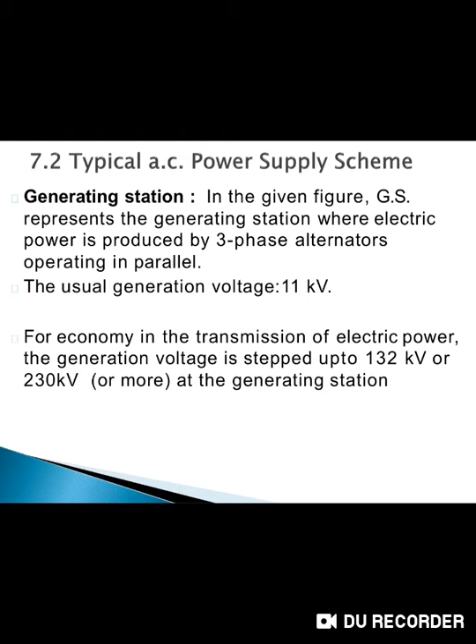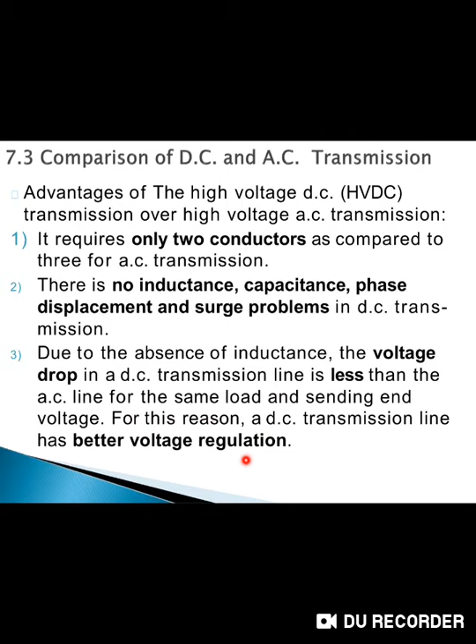We have already known the electrical supply system can be broadly classified into two types, that is AC or DC system, overhead or underground system. Comparison of DC and AC transmission. First, we have to know the advantages of DC transmission when compared to AC transmission. First point, HVDC transmission requires only two conductors as compared to AC transmission. Here, there is no inductance, capacitance, phase displacement or surge problems in a DC transmission. Third point, there is no inductance in an HVDC system. That's why the voltage drop in a DC transmission line is less than in an AC line for the same load and sending voltage. Whenever the voltage drop is less, the transmission line shows better voltage regulation.